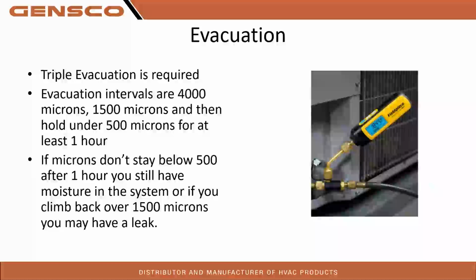Triple evac is, Mitsubishi can say, required. I would say definitely recommended. If you're on a brand new job and you just ran your line sets, never been used before, do you have to do a triple evac every time? Maybe not. It's going to be up to you guys. If you're able to pull it down, get it under 500 microns and it stays, you might be okay.